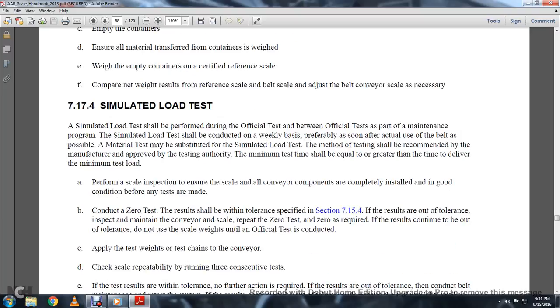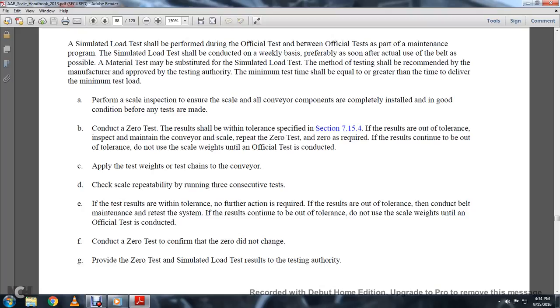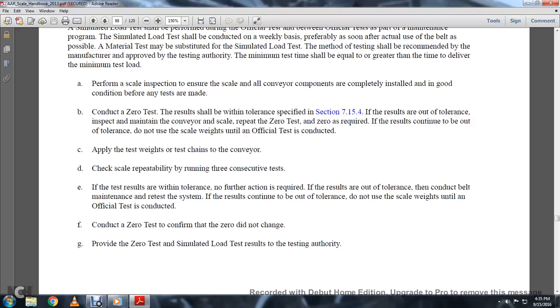Section 7.17.4, Simulated Load Test. A simulated load test shall be performed during the official test and between official tests as part of the maintenance program, conducted on a weekly basis preferably as soon as possible after the belt is actually used. The material test may be substituted for a simulated load test. Inspect the scale and all conveyor components to confirm they are completely installed and in good condition before testing. Conduct a zero test; if the result is within tolerance, apply the test weights or test chains on the conveyor. Check scale repeatability by running three consecutive tests. If results are out of tolerance, conduct belt maintenance and re-test. If results continue to be out of tolerance, do not use the scale for weighing until the official test is conducted.